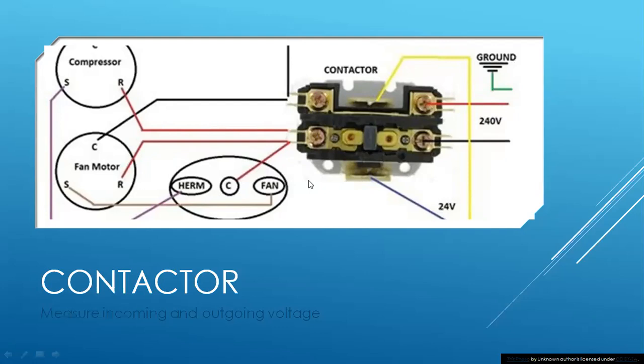Now, I've had this actually a few times lately, where guys are replacing compressors and capacitors, where they're putting them in and they're not wiring this up exactly the way it should be. Follow your diagram on your unit. If you don't wire it up by the unit, a lot of times these guys are putting new compressors in and they're getting what appears to be lock rotor amps, because for some odd reason they're not getting their common over here to the dual cap.